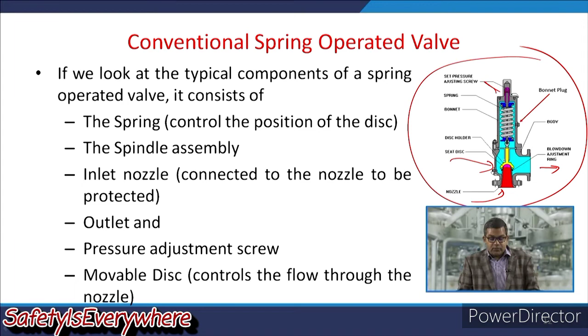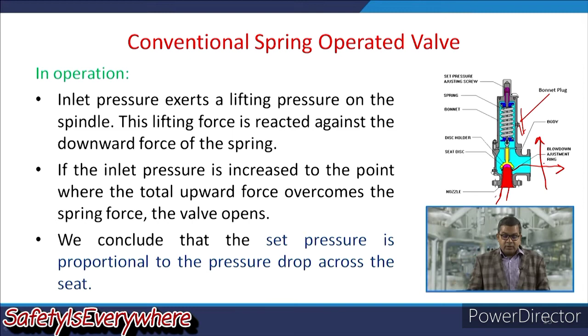Now, considering the operation, the inlet pressure exerts a lifting pressure on the spindle, this one. The lifting force is reacted against the downward force of the spring, which, based on the spring constant, exerts this downward force. If the inlet pressure is increased to the point where the total upward pressure overcomes the spring force, then the valve opens, and the fluid may come out from this zone to this one. So, I conclude that the set pressure is proportional to the pressure drop across the seat.